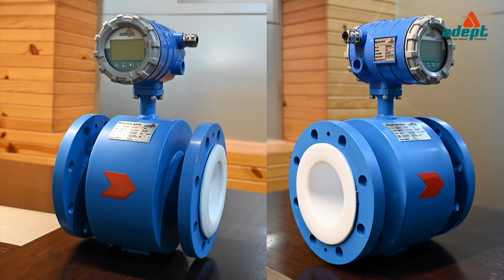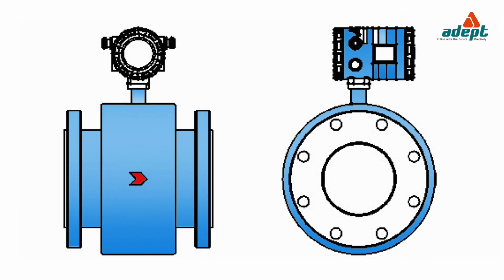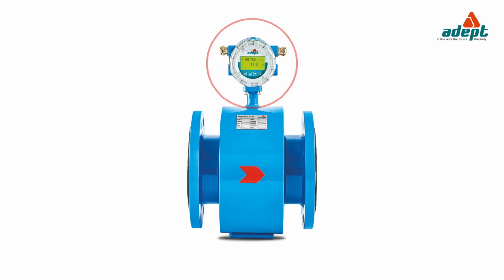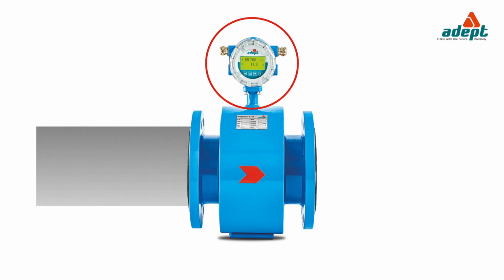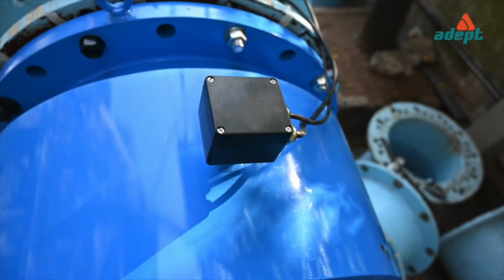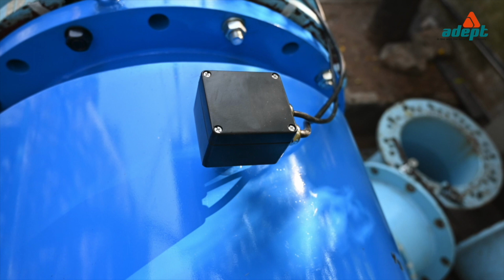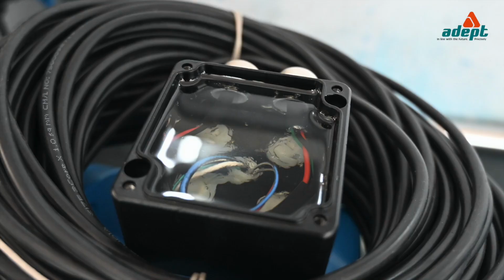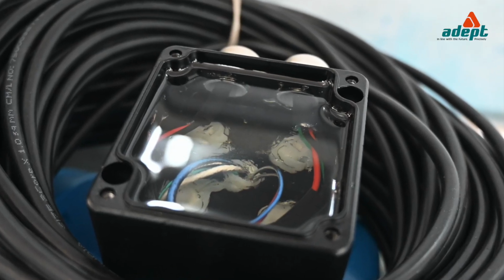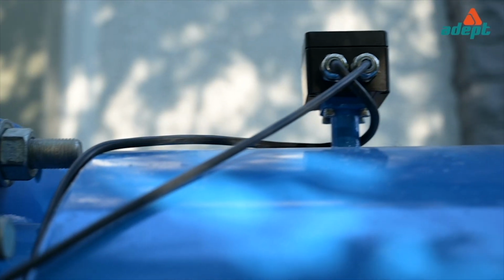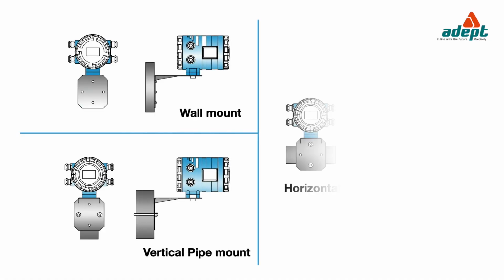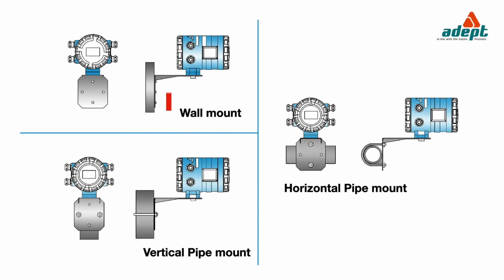In the case of an integral type flow meter, the transmitter comes pre-mounted atop the flow tube and therefore gets physically installed along with the flow tube. However, in the case of a remote type flow meter, a junction box comes pre-mounted atop the flow tube. The coil and electrodes cable is delivered connected to the junction box. The transmitter along with its mounting bracket is delivered separately.